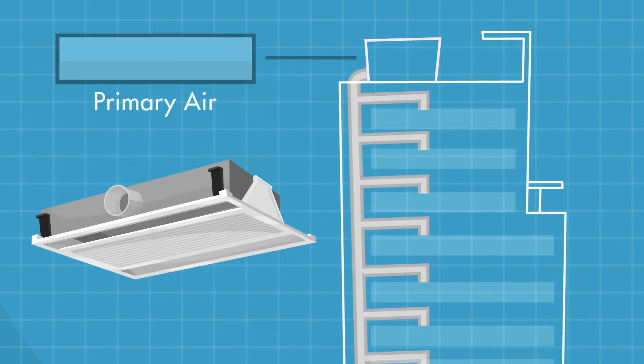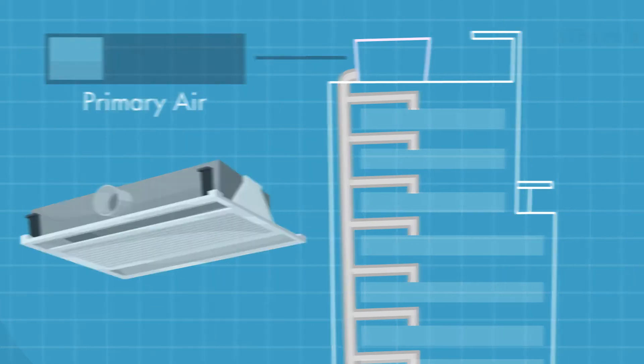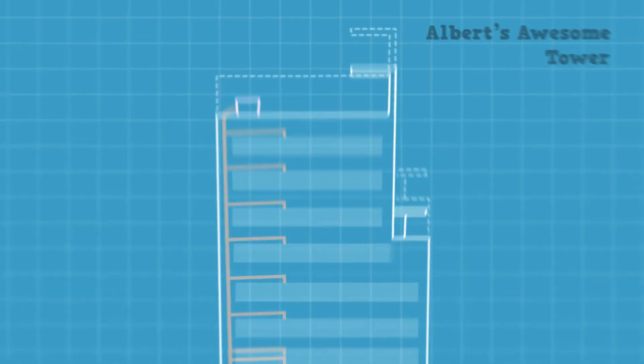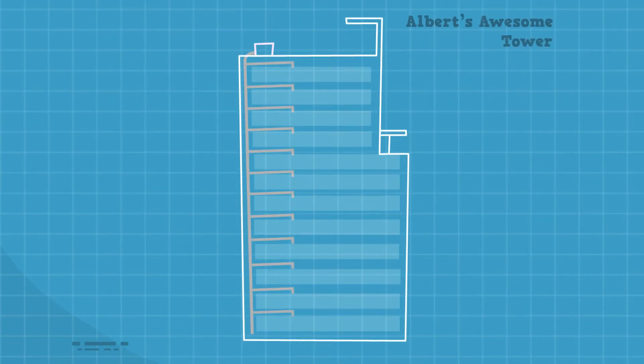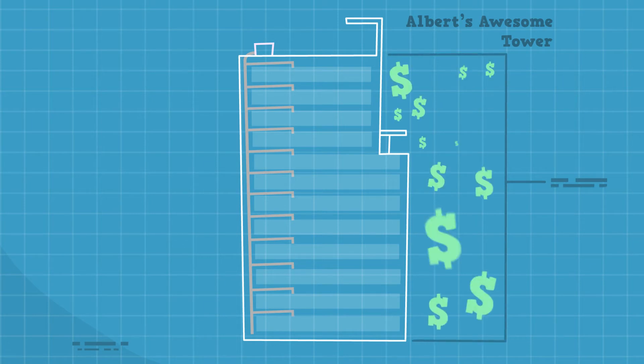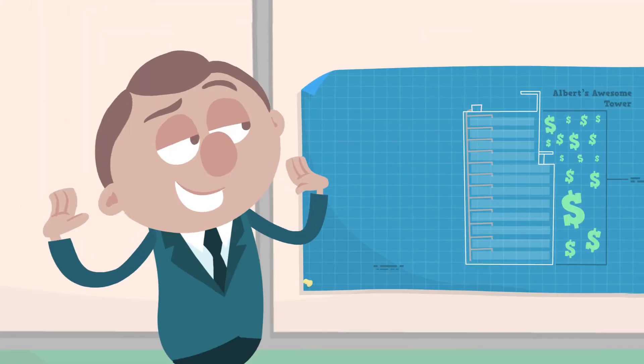Second, while active beams still require dehumidified air from the central plant, they require a lot less primary air, meaning lower fan power and smaller ductwork. This allowed Albert to fit more floors into his building spec. And more floors means more leasable office space. You go, Albert!